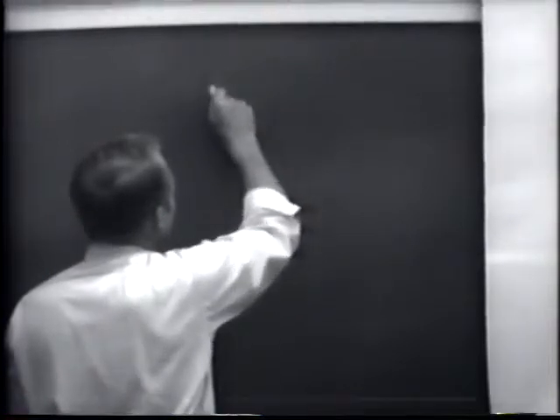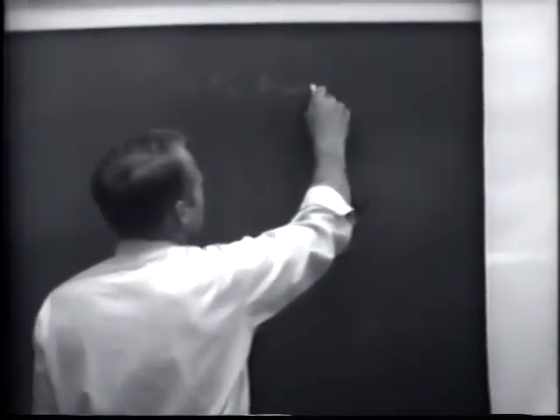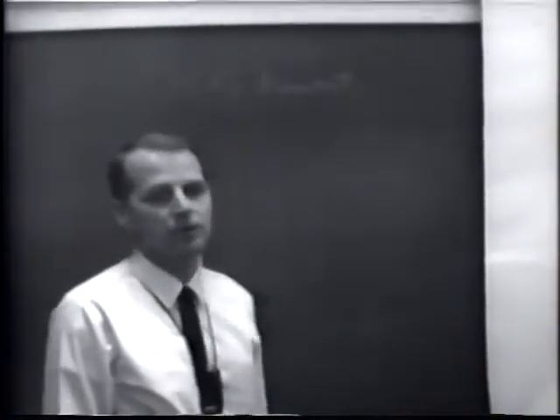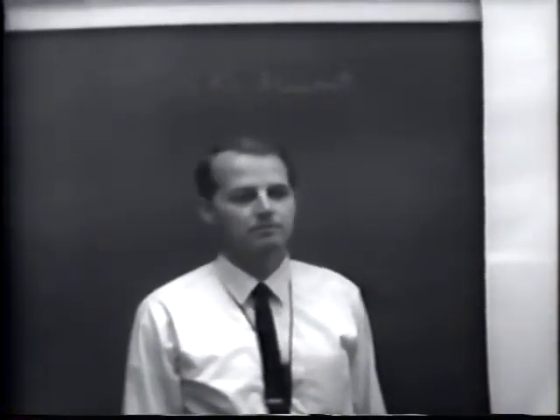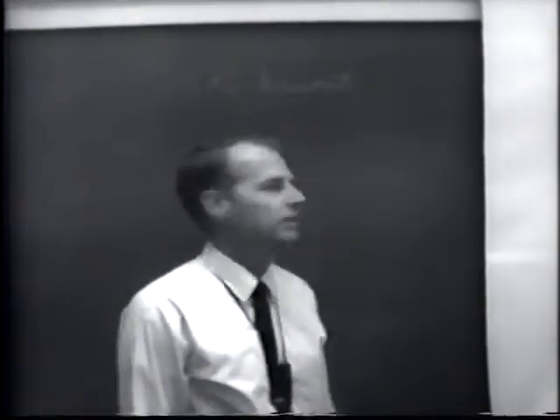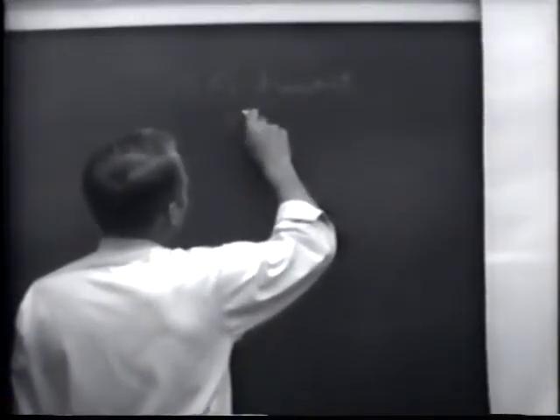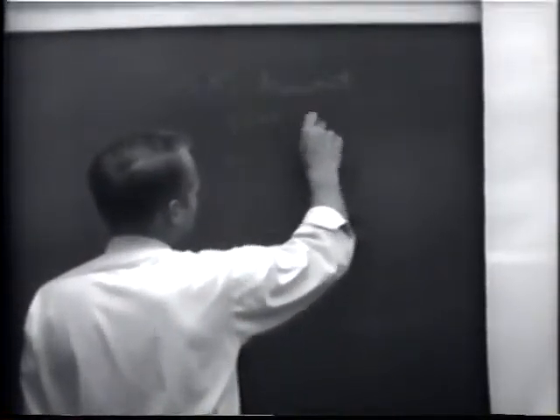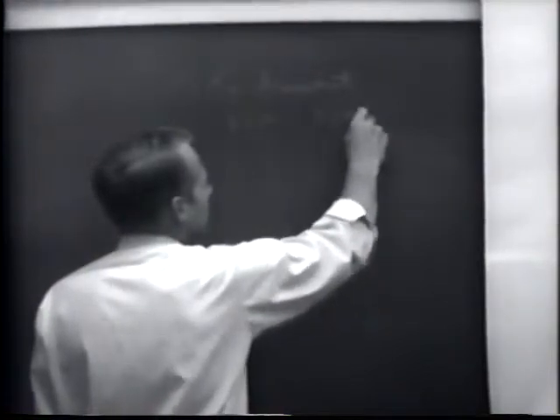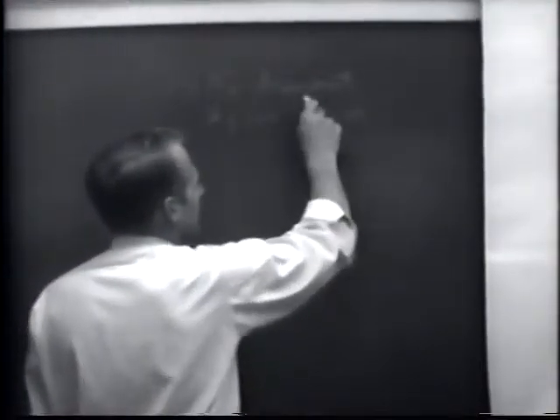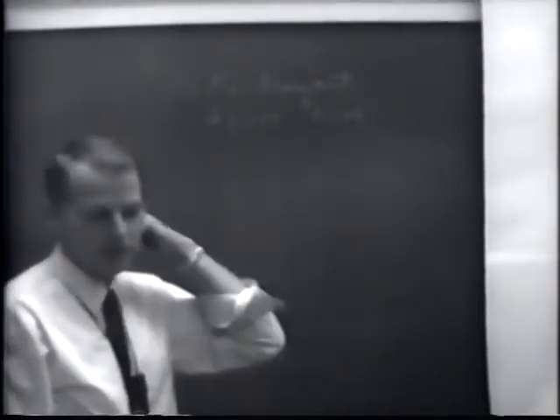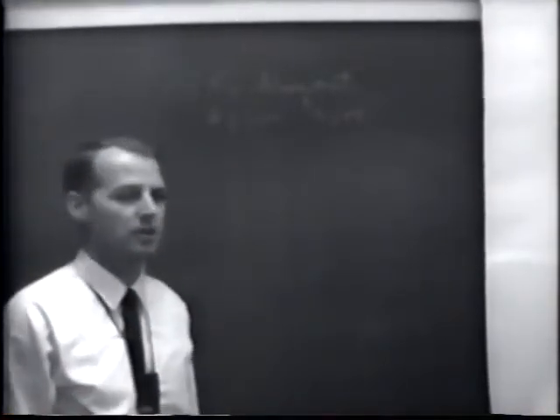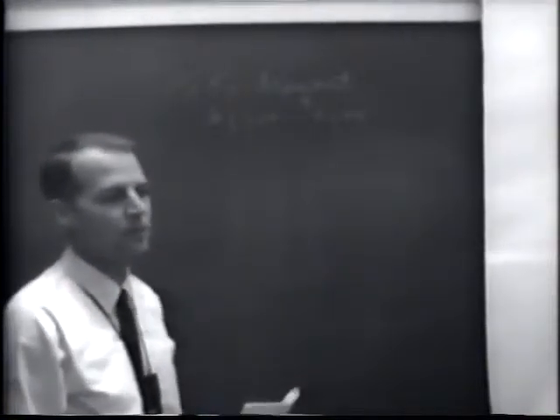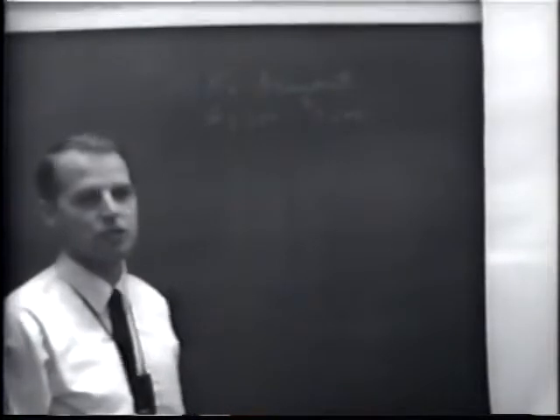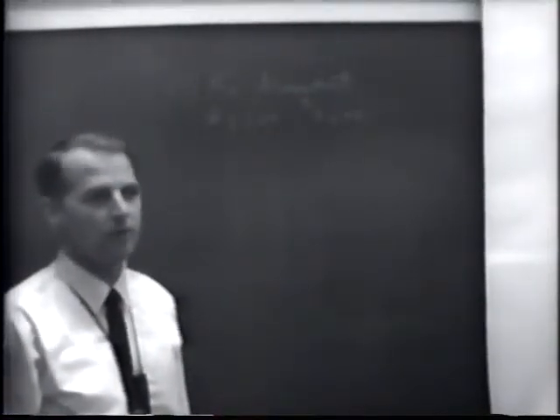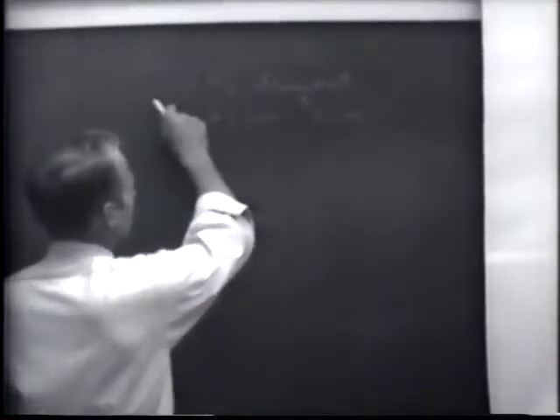Now, the 15 kV draw-out breakers, the breaker alone, without the switchgear cell that it belongs in, is in the order of $3,500 to $4,600. This is not a figure that would compare with some of the other costs I'm going to put up here, because this is the breaker alone, and it's going to be mounted in a switchgear cell, and the total cost would vary quite a bit. But breaker alone on a 15 kV draw would be something like this.